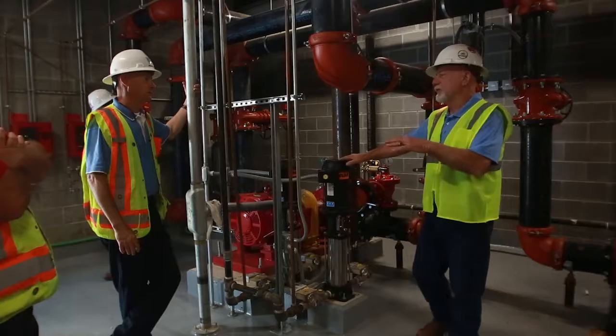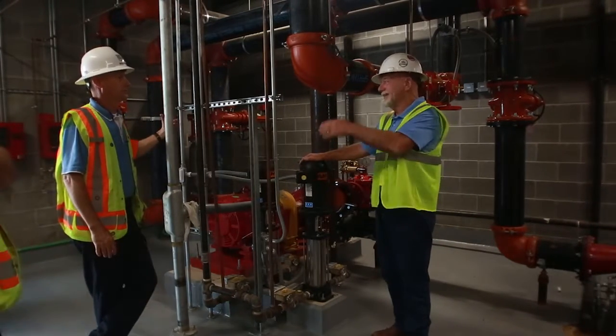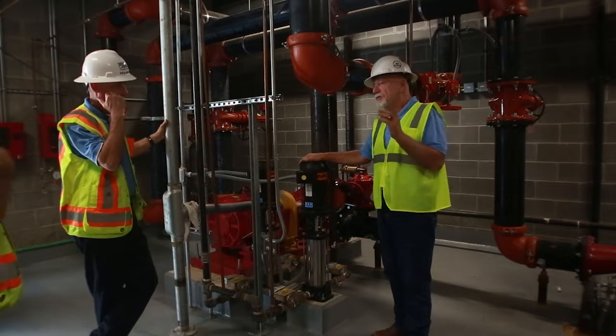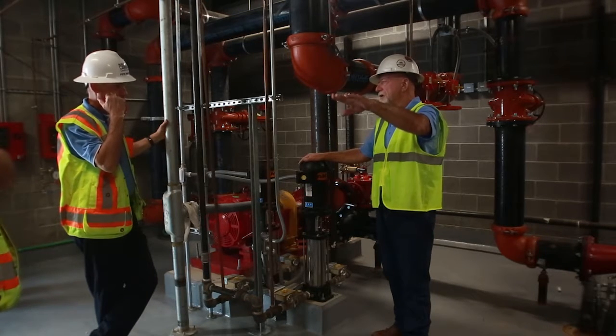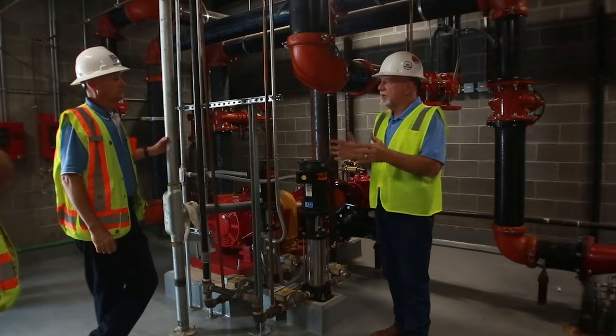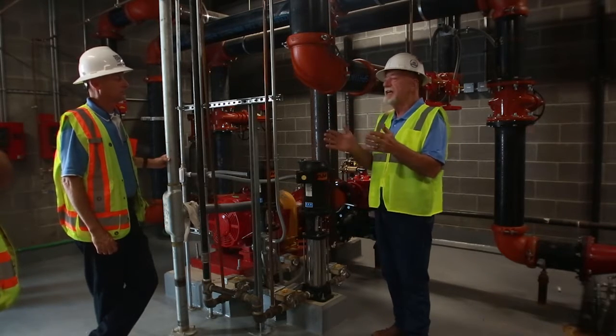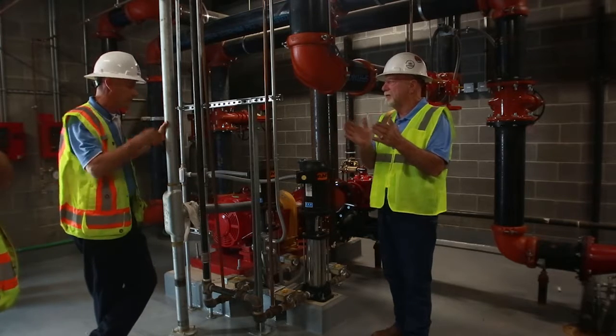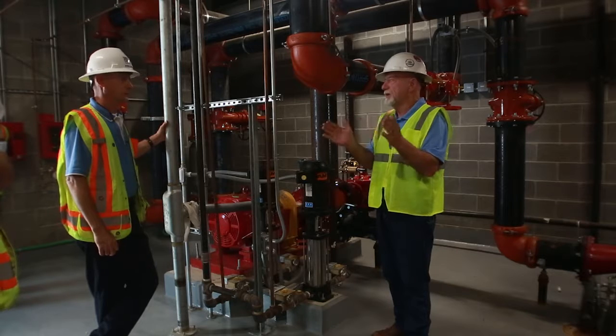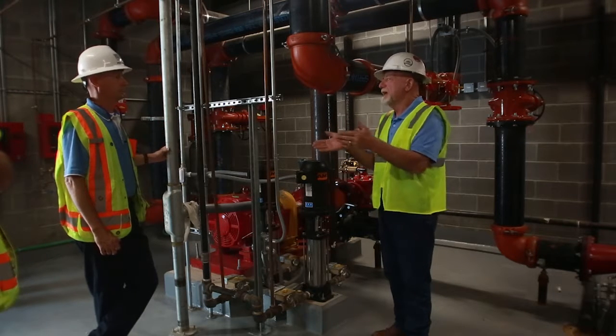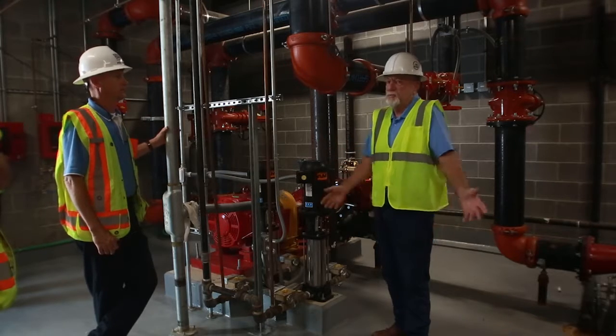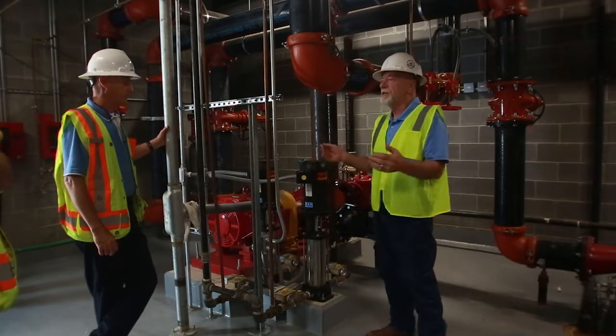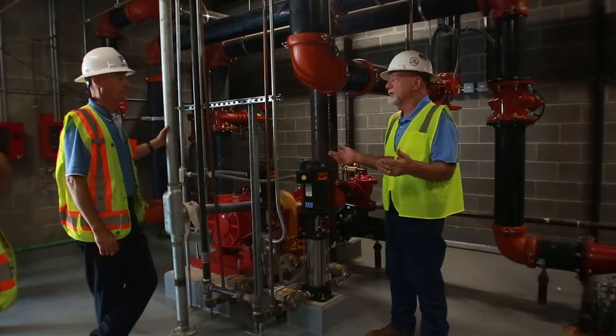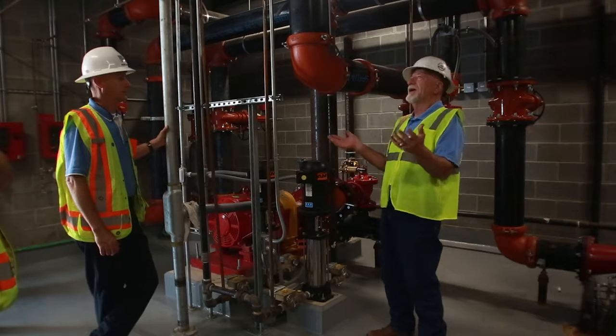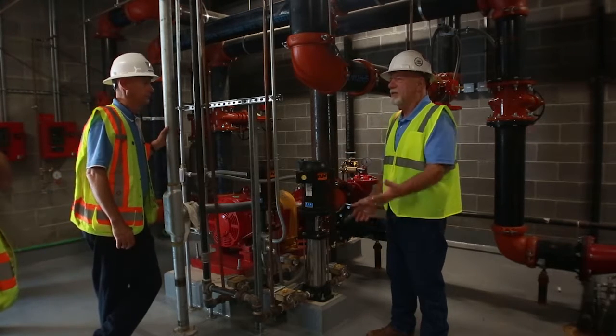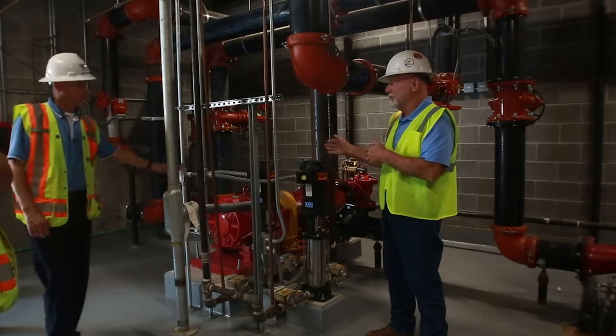Okay, well, there's two different ways to address it. One is having identified that's what the issue is, you can reprogram the computers and the controllers. Number one, you can take the jockey pump and increase that pressure so that at any given time, that jockey pump is going to put out 155 or 160 pounds of pressure, period. That's always. Because you shouldn't have to have that problem every time you walk into a room. Can you imagine if you didn't know the building, you'd walk in there and destroy the whole place and not know it. Right. So it needs to be addressed through programming.